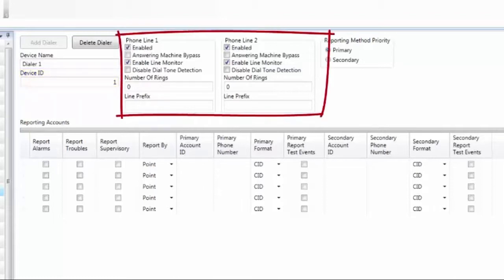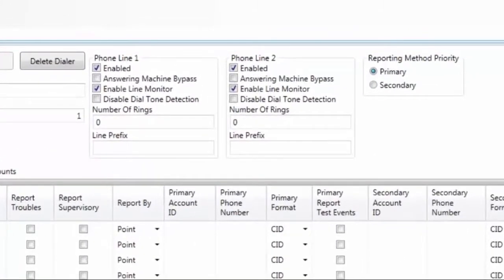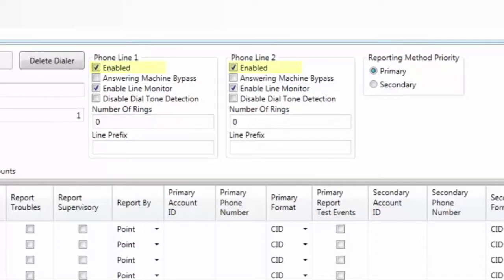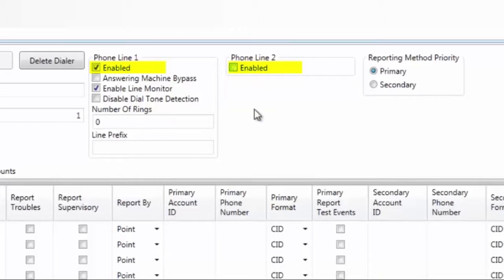Moving to Phone Line 1 and Phone Line 2. This is where we can adjust the settings for the phone lines that are provided by the phone company and connected to the UD1000. Your first option is Enabled. The default is Check. When this box is checked, the jack on the UD1000 is active and can be used for communicating to a central station. If, for example, you are only using one phone line and you want to disable Line 2, simply uncheck the box and Line 2 will be disabled.